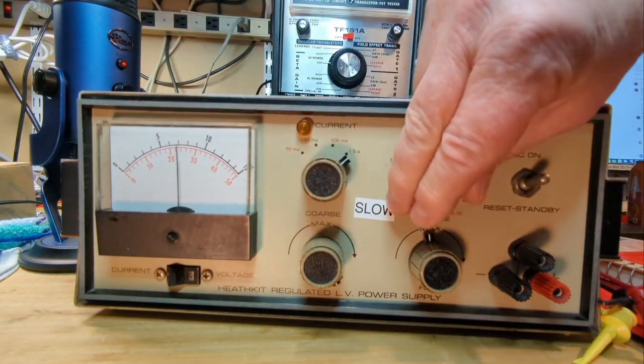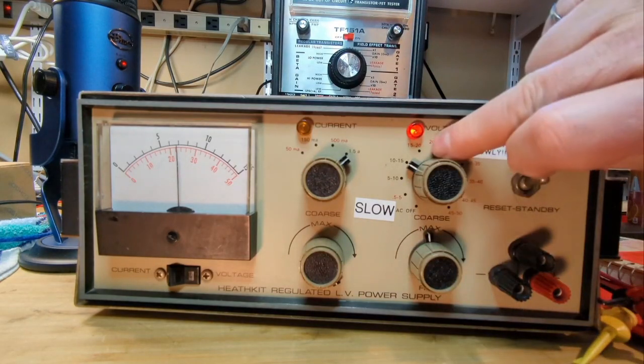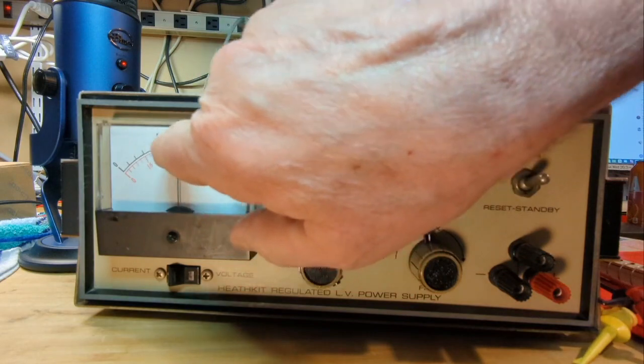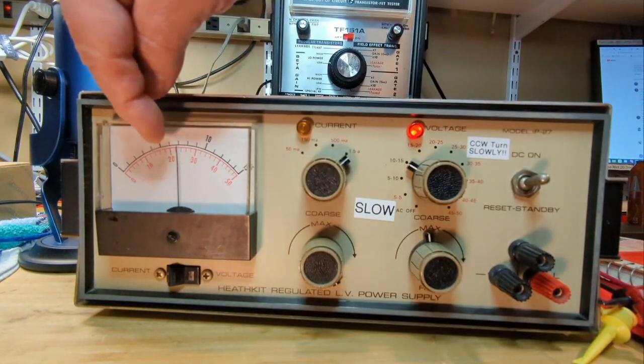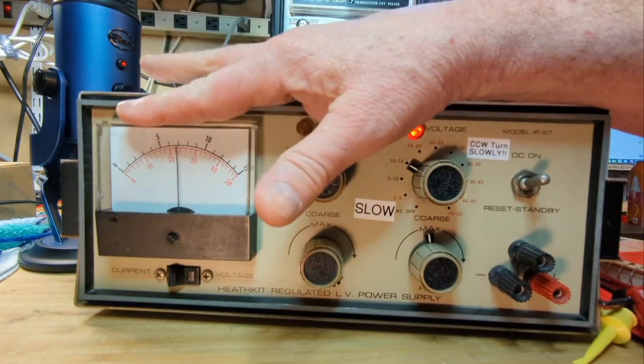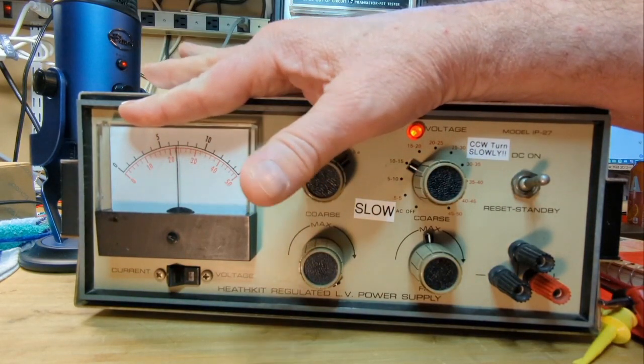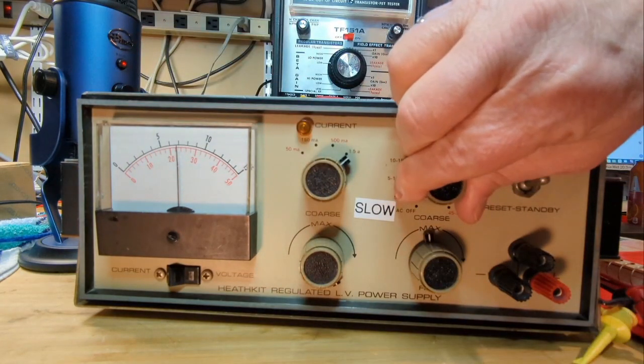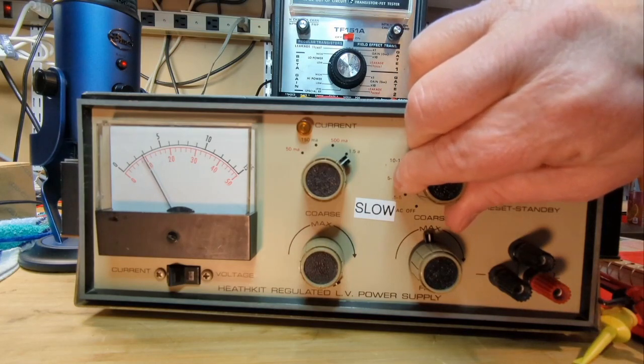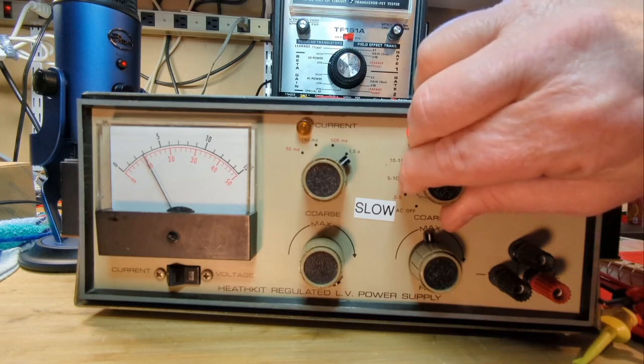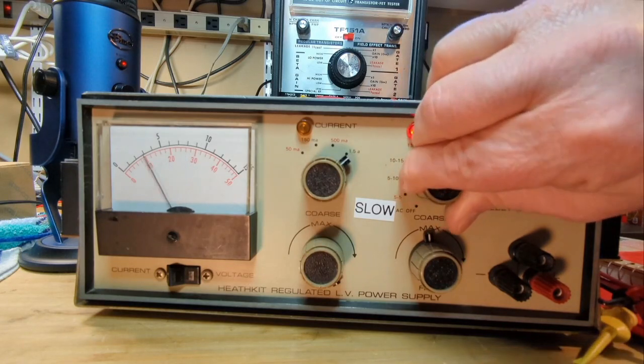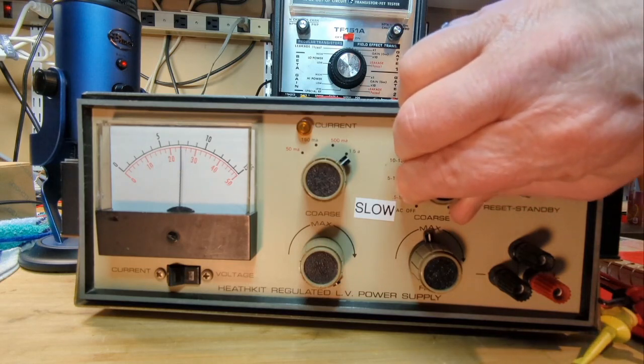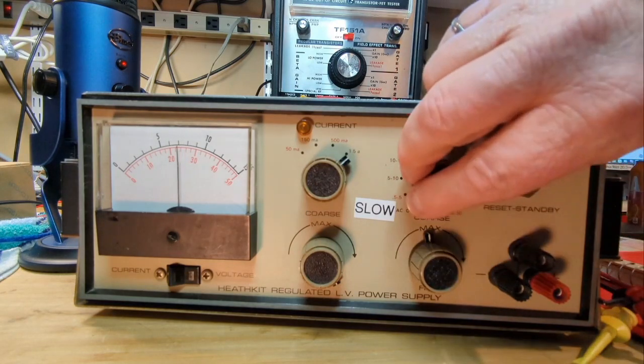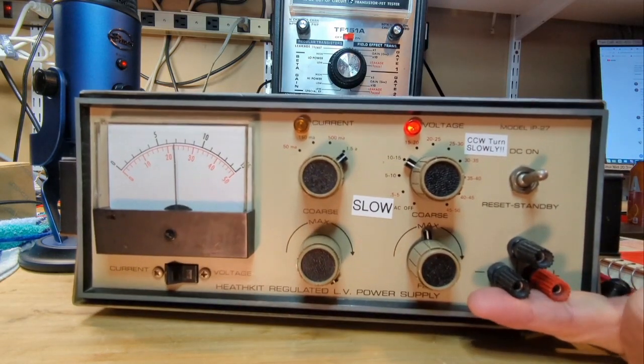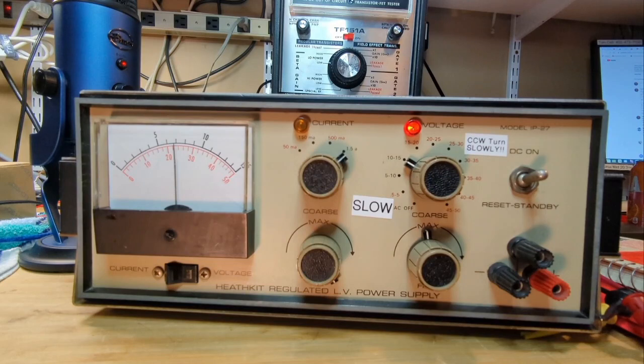6. So I thought, I'll turn it up, see what happens in the 15 to 20 volt range, which would put me between 15 and 20 volts in the red range, which is way down here. The meter, by the way, on something like this is meant just for a guideline. You should use your voltmeter to dial in your voltage exactly, but you need to kind of know where you're at. So I turned it up. Listen. Very faintly, there's a click in there. Hear it? No, it's not my switch making that noise. That's the overcurrent relay grumping at me that it's throwing into overcurrent, and I have no load on it yet. So that's a problem.